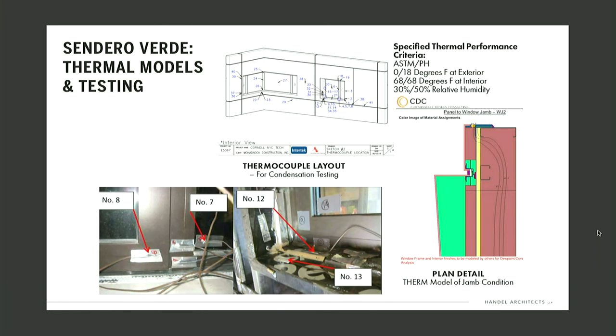To do these windows, you have to put your facade through the ringer. This is a PMU, we're doing thermal model testing — these nodes measure temperature to verify what we're doing. You can see a couple of these points right here, that's one of the vertical stacking joints, and that was the least-performing spot. The PMU told us we needed more insulation there, so with that service cavity, we pumped insulation in to make sure we were meeting our comfort criteria inside the apartments.